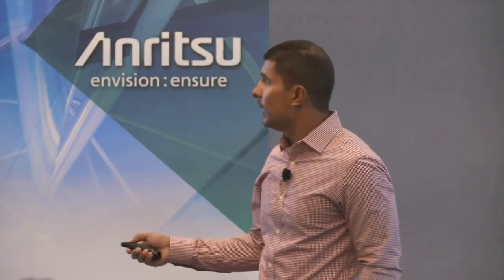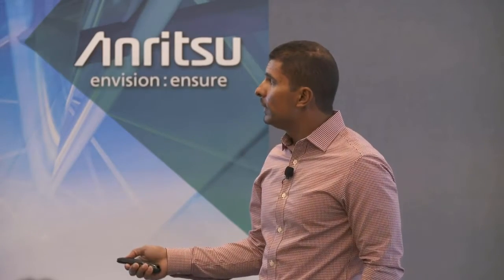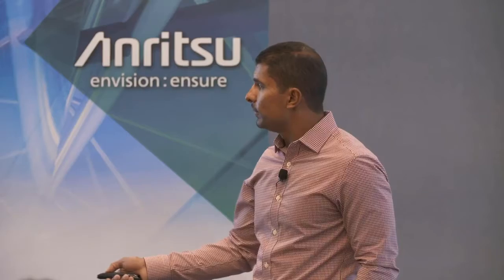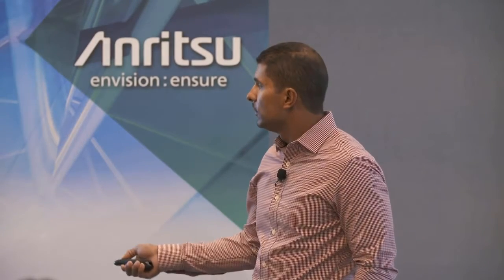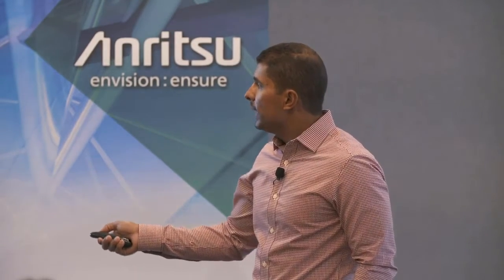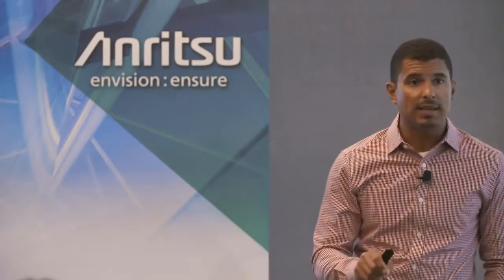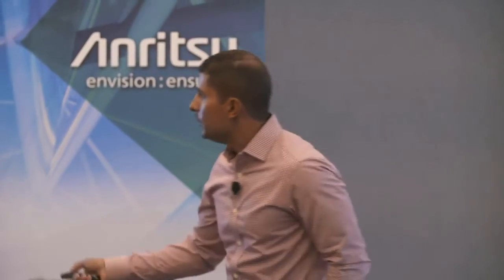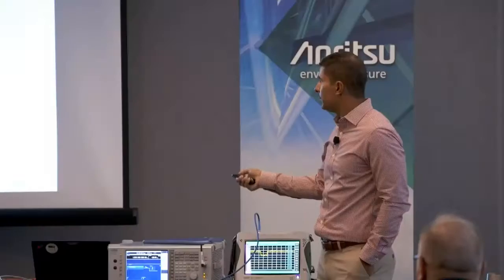Well, here's the problem with that. When you're setting that, and everyone has to do it, by default, most of these, and I use a couple of different examples here, Microchip, Trimble, Seiko, each one has a setting for that antenna cable delay. That's basically, once that T0 from the GPS hits my antenna, how much of a delay is it for my antenna going all the way down to my grandmaster? Because we have to take that into consideration. In most cases, these settings are by default 0.